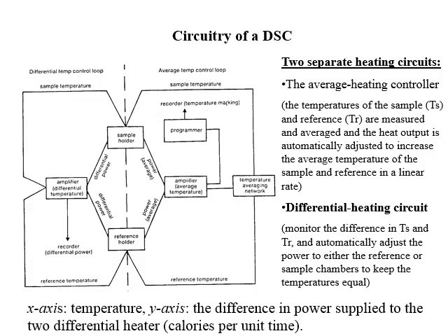Not going to really talk about this diagram too much. I don't think there's really any point. As I said on the previous slide, you basically have two separate heating circuits. One heats the sample, one heats the reference, and you monitor the difference.